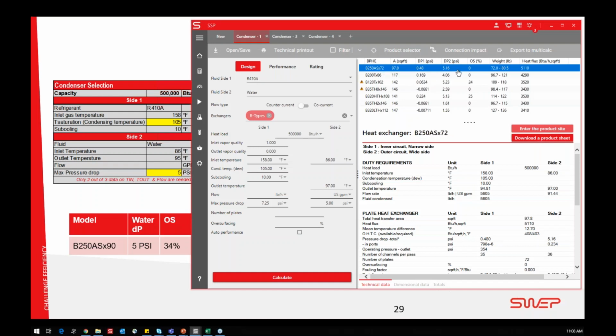Now this is almost a perfectly balanced heat exchanger. We reach the 5 psi, plus a little bit of bonus with compliments of SWEP, and an over surface of 0. So in this case, having 91 GPM instead of 112, allowing for a slightly hotter water outlet temperature, you can save 18 plates if you want to.